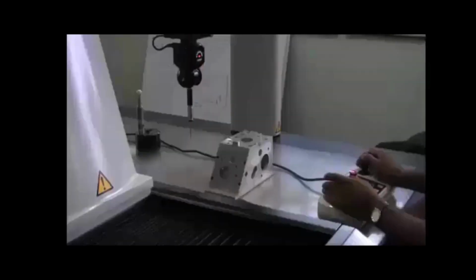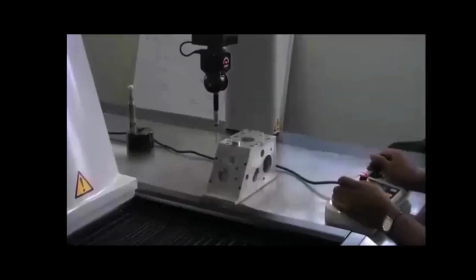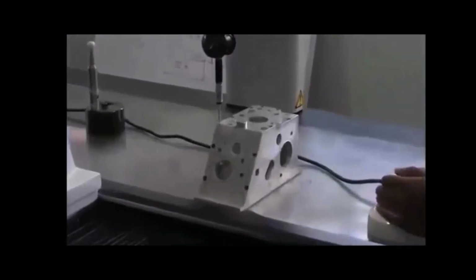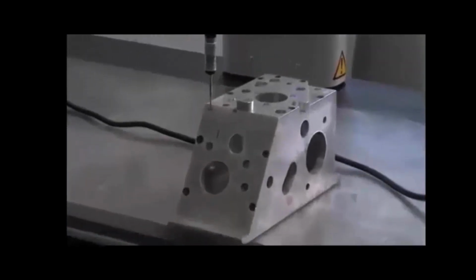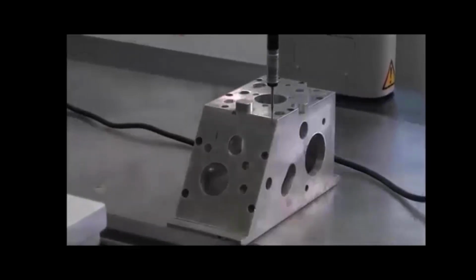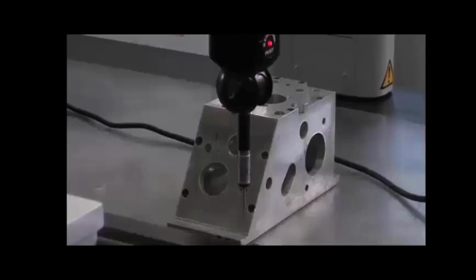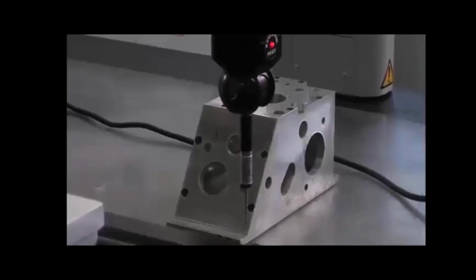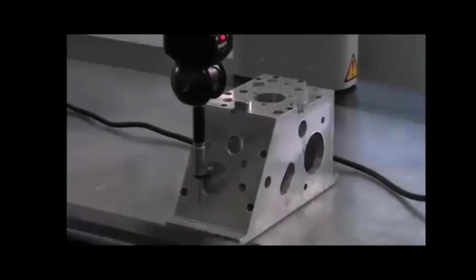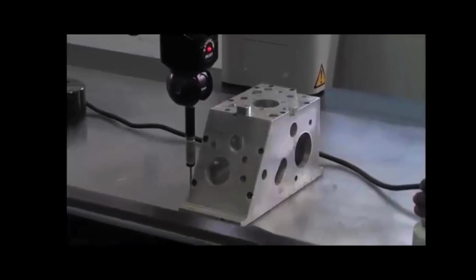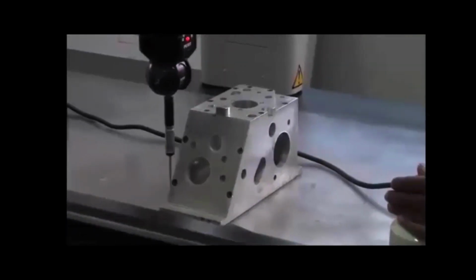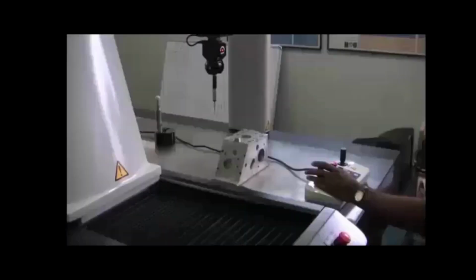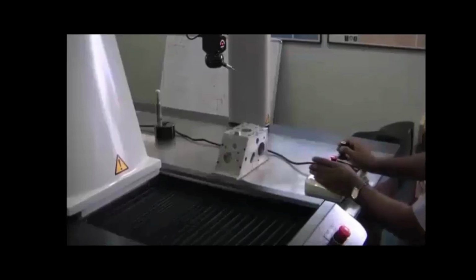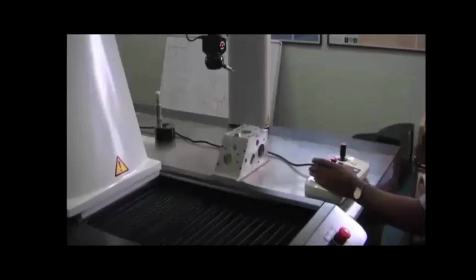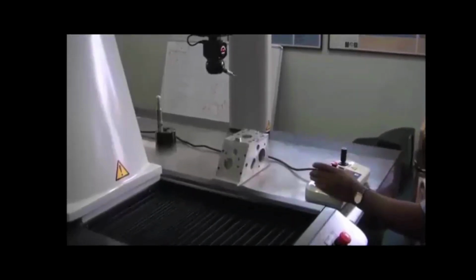Before using the probe, we should calibrate. Now you can see the operator is operating the joystick. He is moving the stylus and inspecting the inclined surface on the workpiece. The stylus is contacting at 4 different places of the inclined surface. When the probe touches, we can see the red light blinks. Now after this, the inclination is calculated and the probe is adjusted for proper orientation.